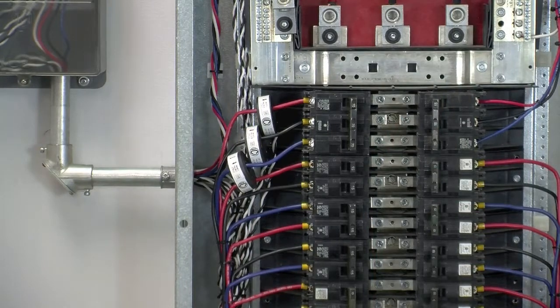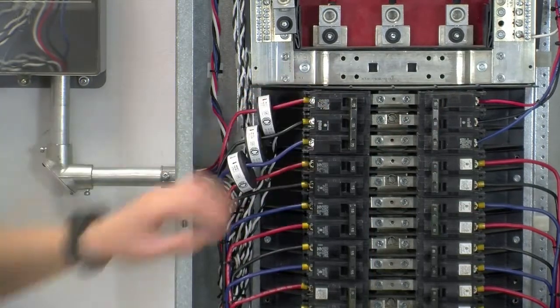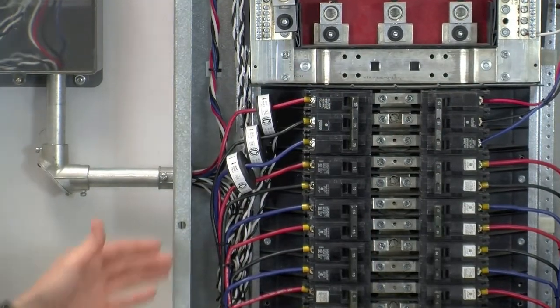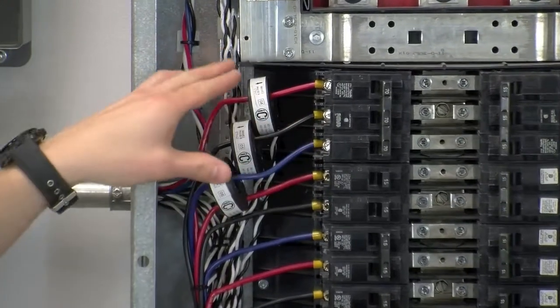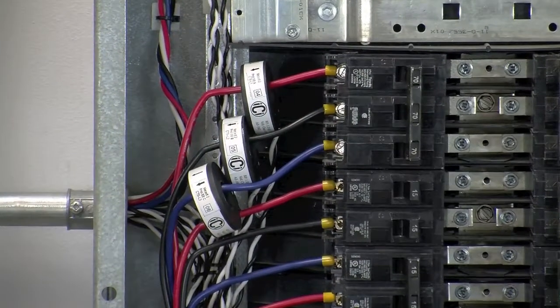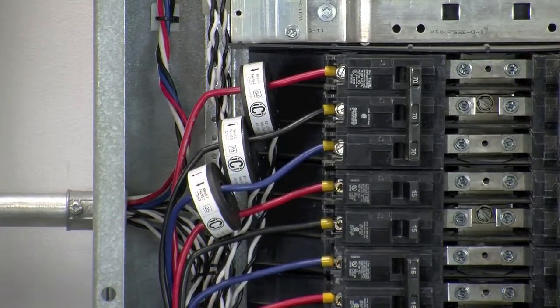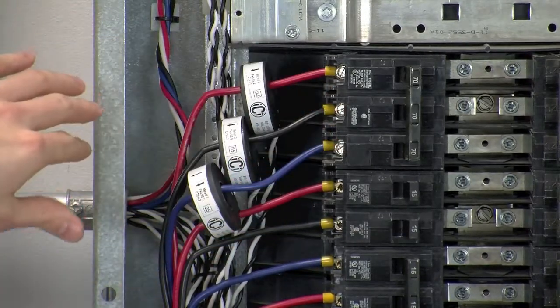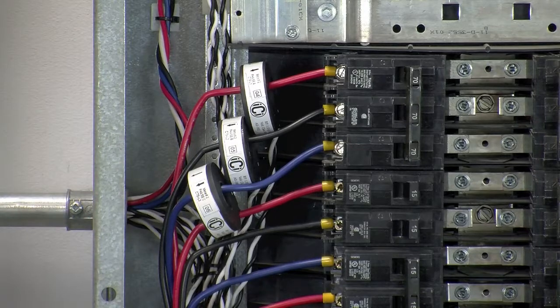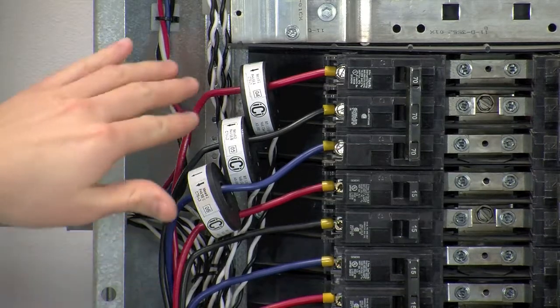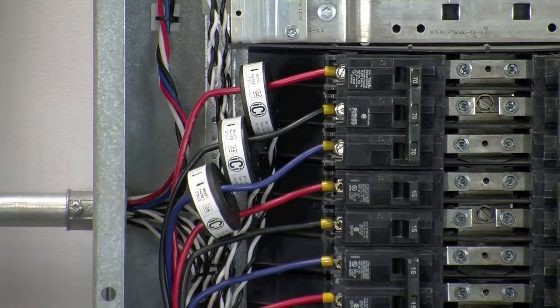Let's pretend for a second that we wanted to meter this three-pole breaker. Once again, you're going to repeat the phase test for the breaker intended and install the CTs accordingly. But just keep in mind that for CTs on breaker loads, the arrow must point away from the breaker as current flows out from the breaker towards the load. Unlike our mains that pointed in towards the breaker, our CTs on a breaker load must point away from the breaker.